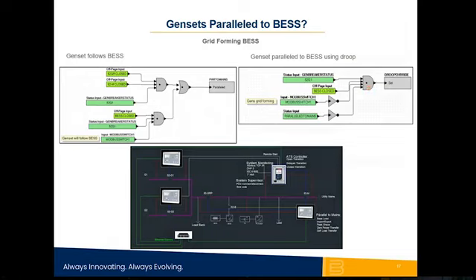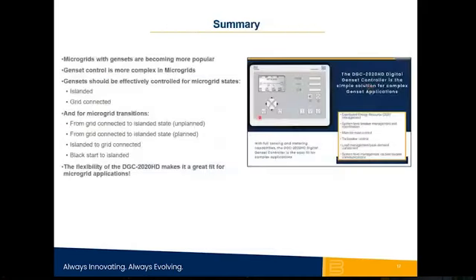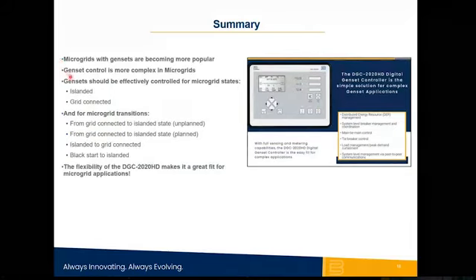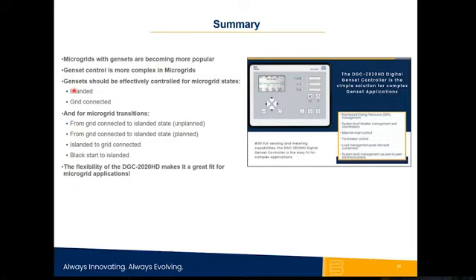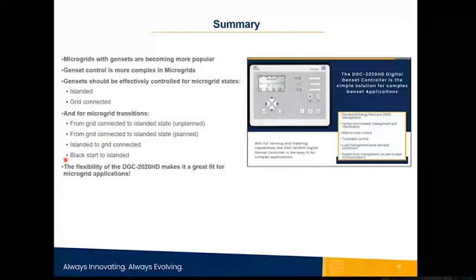So what have we learned? That microgrids with gensets are becoming more popular. Genset control is more complex when you have a microgrid than just a typical standby setup. Genset should be effectively controlled for the various microgrid states, which are either islanded, which is disconnected, or grid connected. And for the various transitions, such as grid connected to islanded, unplanned, grid connected to islanded, planned, islanded back to grid connected, or black start. If your transition to an islanded state failed, you go through a blackout period and then transition from black start to islanded. The flexibility of the 2020 HD makes it a great fit for all these various microgrid applications.